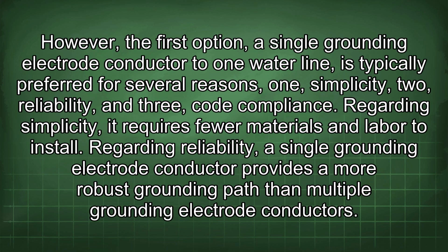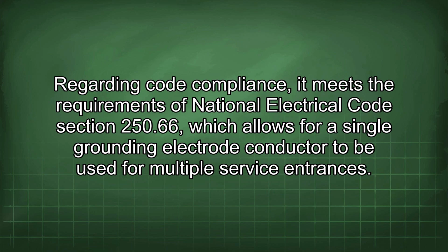However, the first option, a single grounding electrode conductor to one water line, is typically preferred for several reasons: 1. Simplicity, 2. Reliability, and 3. Code compliance. Regarding simplicity, it requires fewer materials and labor to install. Regarding reliability, a single grounding electrode conductor provides a more robust grounding path than multiple grounding electrode conductors. Regarding code compliance, it meets the requirements of National Electrical Code Section 250.66, which allows for single grounding electrode conductor to be used for multiple service entrances.